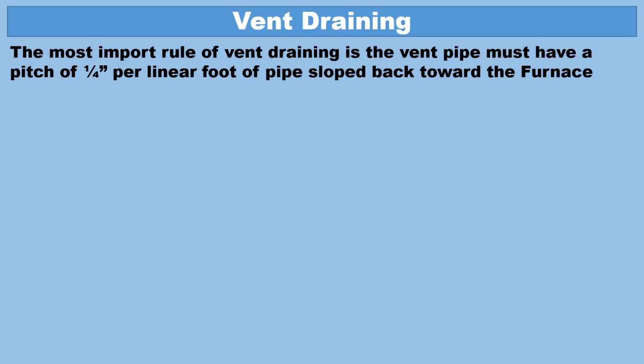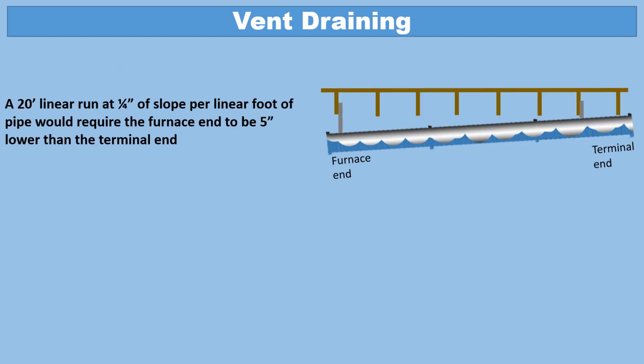The most important rule of vent draining is the vent pipe must have a pitch of 1/4 inch per linear foot of pipe sloped back towards the furnace. A 20-foot linear run at 1/4 inch of slope per linear foot of pipe would require the furnace end to be 5 inches lower than the terminal end. And that way you've got your nice little downhill flow back towards the furnace.